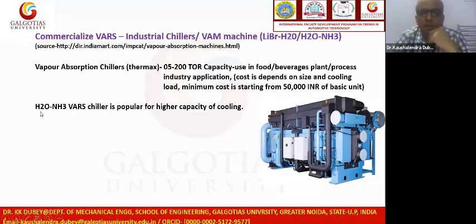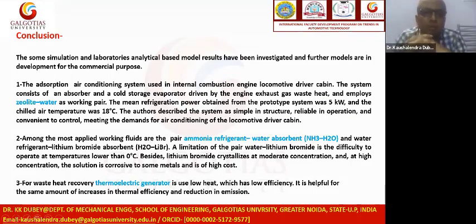For higher cooling capacity, the aqua ammonia vapor absorption machine is very popular for industrial purposes like food, beverages and process industry, automobile industry, and refinery, for cooling of space and for water chilling. That is why we have limited application of the VAM machine. Throughout this discussion, a few conclusions: we have many refrigerant and absorbent materials like zeolite water, ammonia water, and lithium bromide water solution for the vapor absorption cooling machine system.